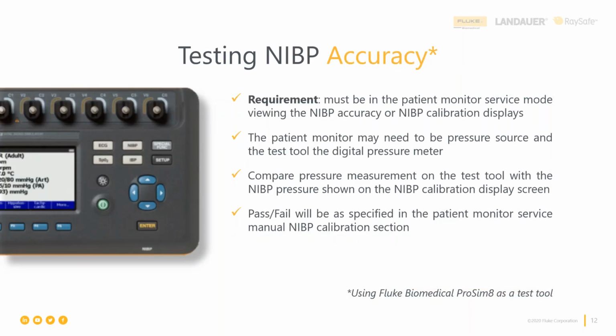All right. So when we go about trying to do static pressure level assessment, perhaps you've already noticed, maybe you've tried this, you find that you can't just connect up your pressurization device or your measurement device to the blood pressure measurement system and get it to hold a pressure. And that's because there's a pressure relief valve in that system that has a normal condition of being open. That means it's not closed. You cannot seal the pressure measurement system. And in order to do a static pressure test, you must be able to seal the measurement system. We call that the vessel, the pressure vessel. You've got to be able to seal it.